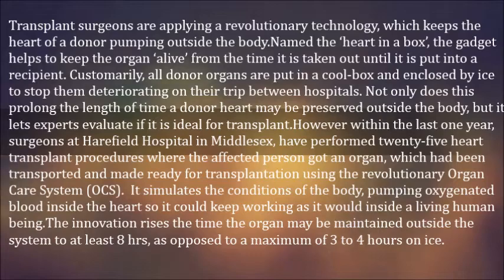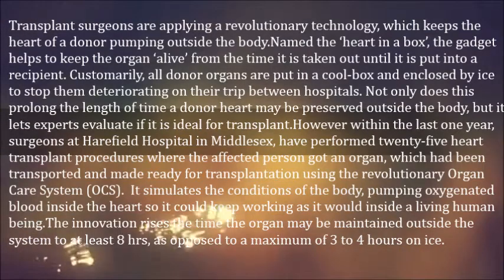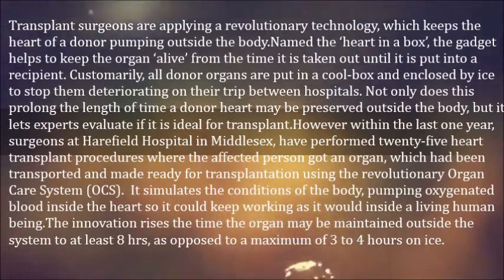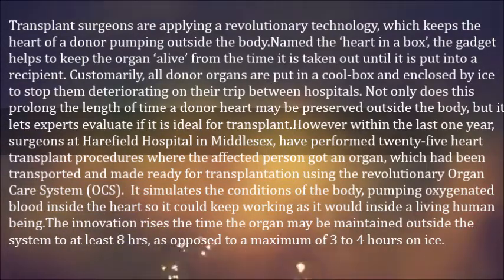Not only does this prolong the length of time a donor heart may be preserved outside the body, but it lets experts evaluate if it is ideal for transplant. Within the last year, surgeons at Harefield Hospital in Middlesex have performed 25 heart transplant procedures using the Revolutionary Organ Care System, which simulates the conditions of the body by pumping oxygenated blood inside the heart so it keeps working as it would inside a living human. The innovation extends the time the organ may be maintained outside the body to at least 8 hours, as opposed to a maximum of 3 to 4 hours on ice.